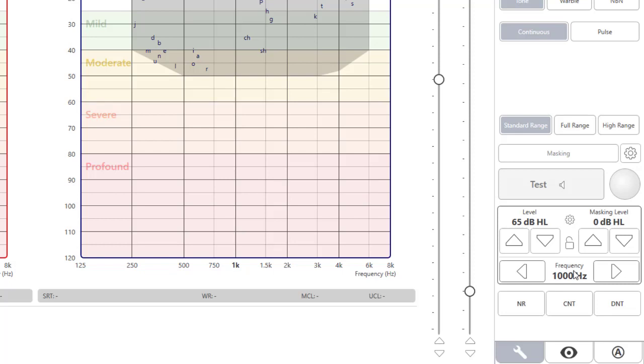To the right of the test bar, there is a circle indicator. The circle will light up or be highlighted when the patient pushes the response button. The circle will also show up highlighted where you are presenting on the screen when the response button is pressed.